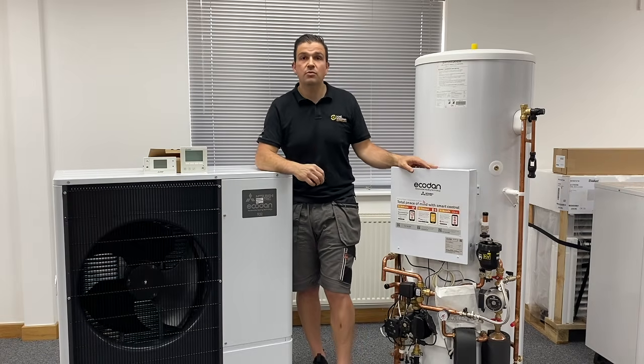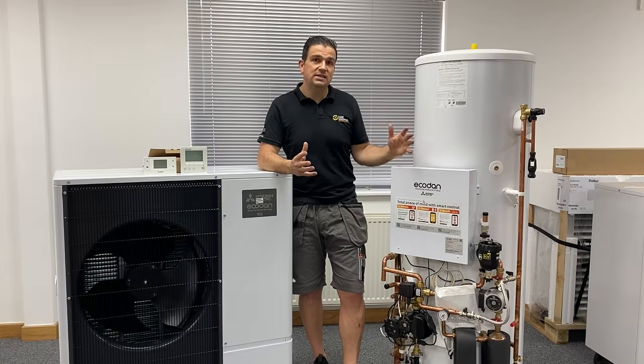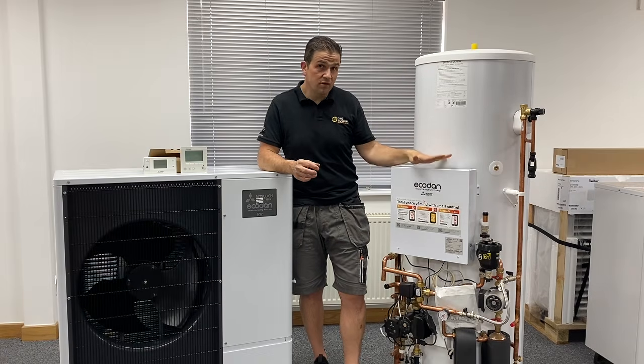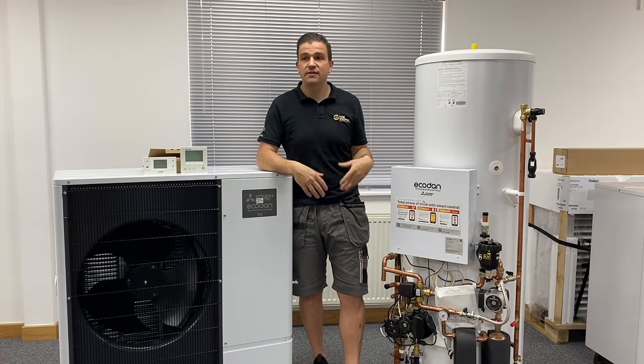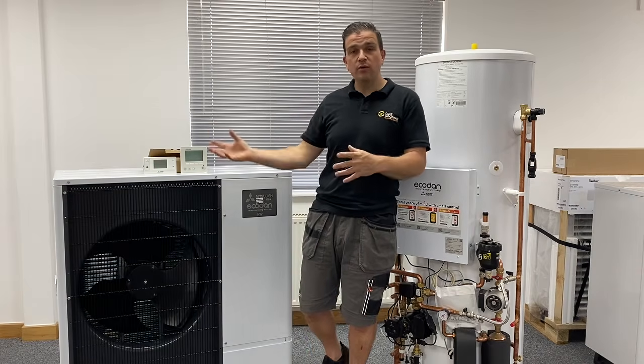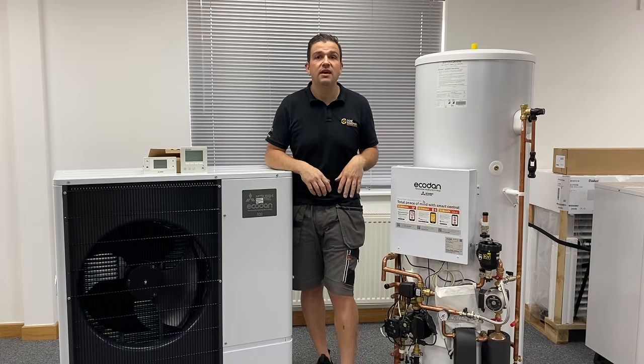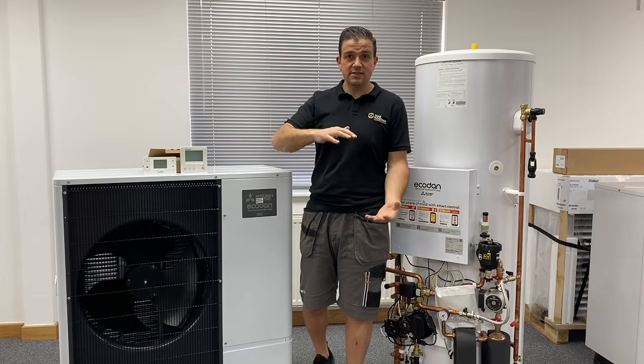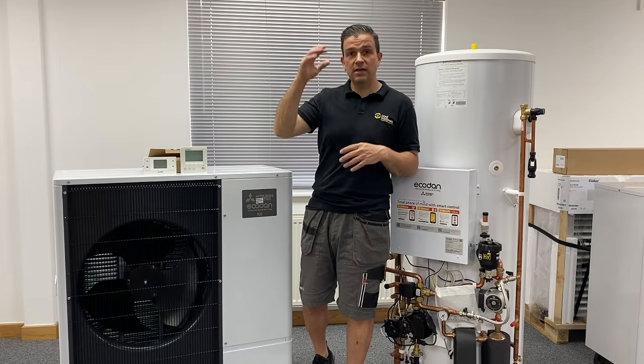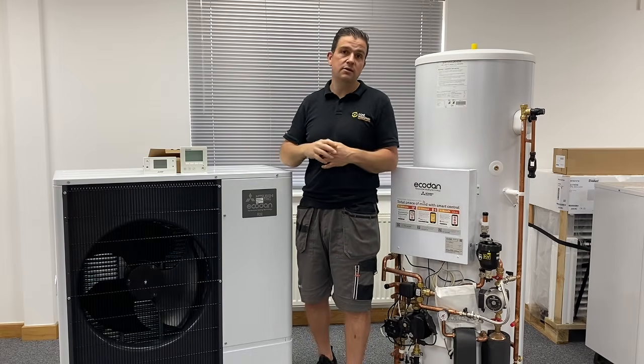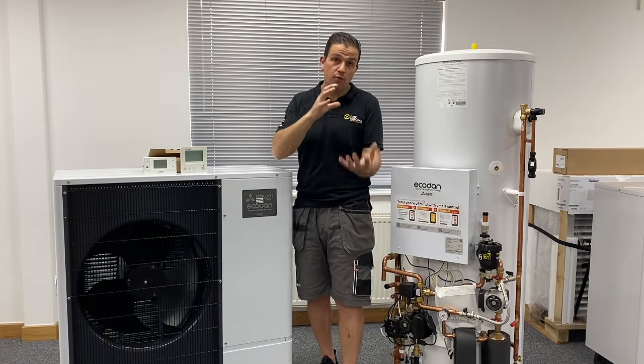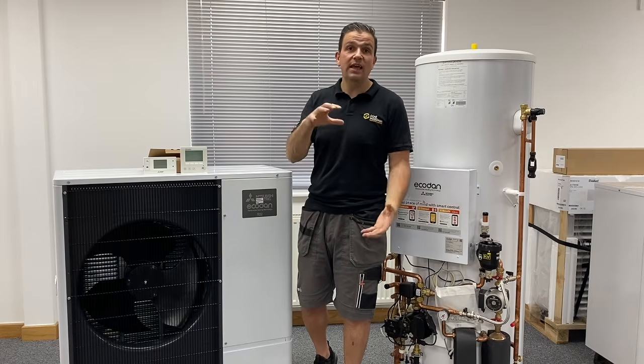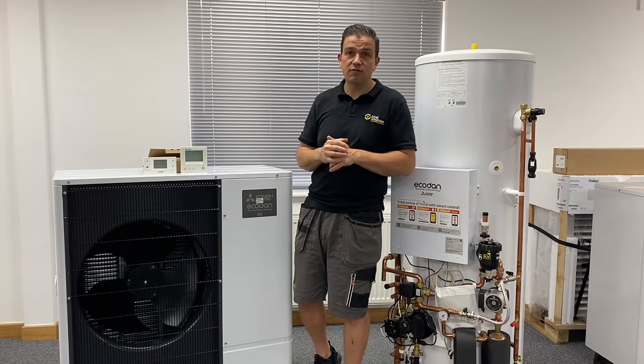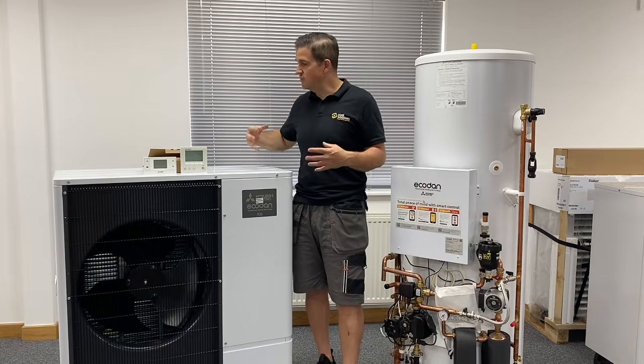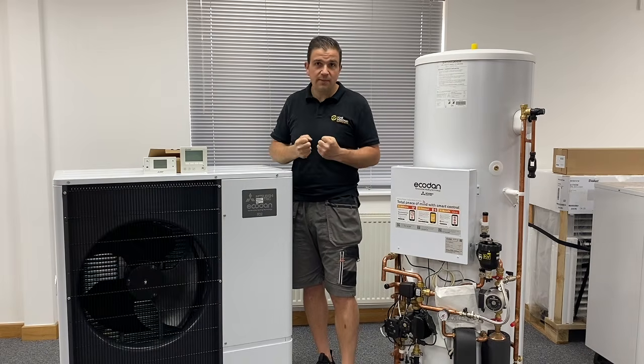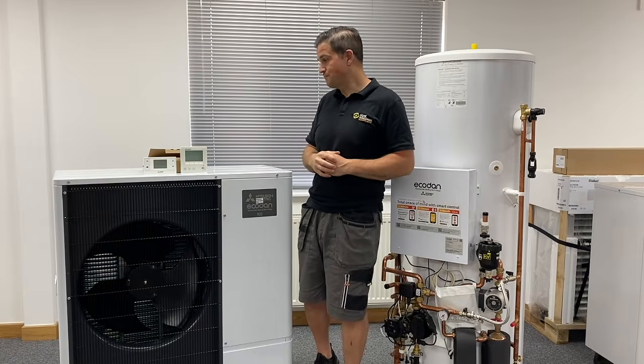The only space that they've got available for a cylinder is an airing cupboard. So we've looked at the size of the airing cupboard and what we can fit in there. Now, with many systems, unlike the Ecodan, a lot of them will require a buffer tank. If you've seen some of our other videos, we install buffer tanks on certain systems because they help with hydraulics, balancing the system and making sure we're getting equal flows into the heating system. It will also use some of the hot water stored in the vessel to help with the defrost. Once the unit is really ramping up and we're getting some frost on the refrigerant pipework, it will withdraw some of that heat and help it to defrost.